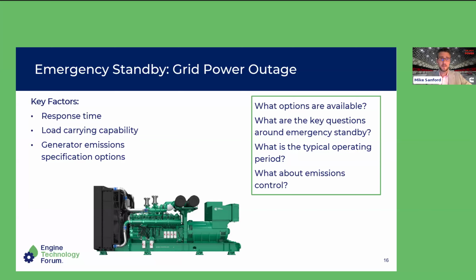Typically, in most years, the generators at a data center site will operate fewer than 20, or even fewer than 10, hours annually. It's not a long period of time, as most data centers aren't built where there is current grid instability — that wouldn't be convenient or economical. So the generator set is truly there to operate in the rare chance that the normal source of power has failed.